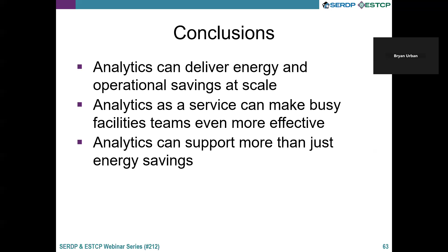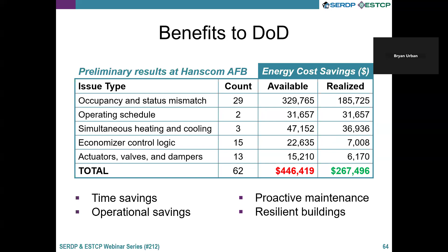As far as benefits to the DoD, these are some example issue counts from Hanscom Air Force Base. Again, we found thousands of issues. Over the year, we really drilled into about 60 or so at Hanscom, and most of them were related to occupancy and schedule. That's where the big opportunities were. Some simultaneous heating and cooling, economizer logic, and actuators, valves, and dampers that were misbehaving. Altogether, we found about $500,000 in savings opportunities at Hanscom. And in the span of about a year and a half, we realized about half of those. So very effective working with the teams on a very lightweight basis. We were able to drive some of these savings and get results.